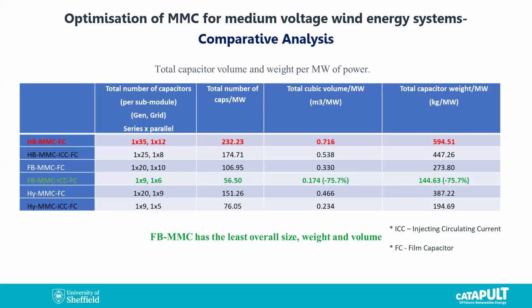This is maybe interesting, because when we did the optimization our target was to look at the volume and weight of the required capacitance for our MMC. This table shows a comparative analysis, starting with the classical MMC, shown in red in the top row, then some optimized improved models, and finally those highlighted in green. This is the full bridge MMC optimized, also with a circulating current injection approach, to further reduce the energy storage requirement. We managed to significantly reduce the size of the required capacitance by 75+%, quite a significant reduction in size.